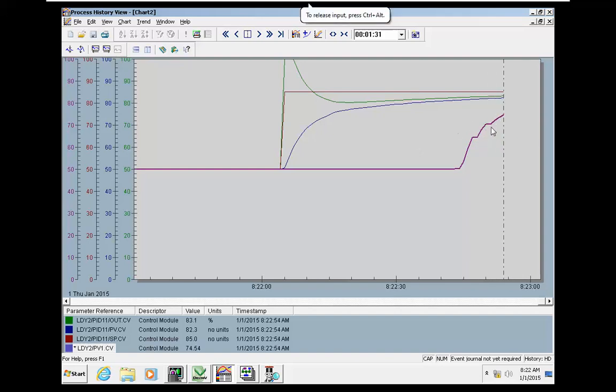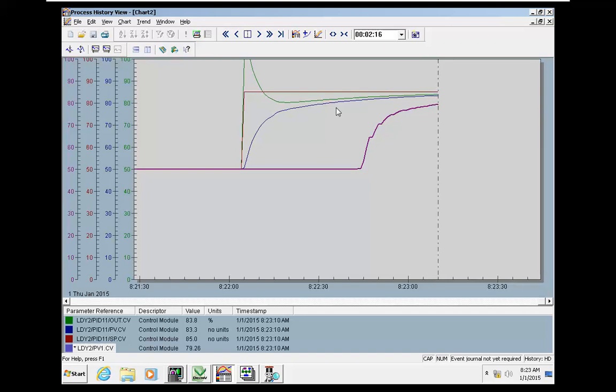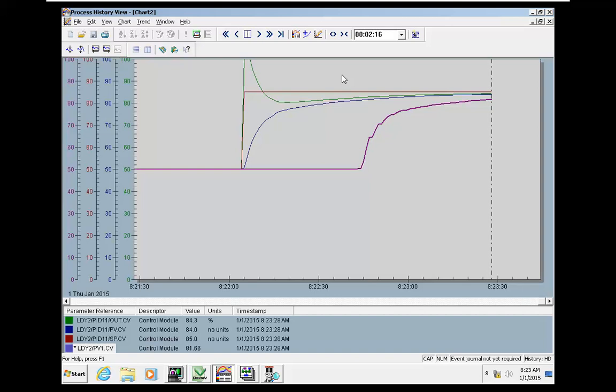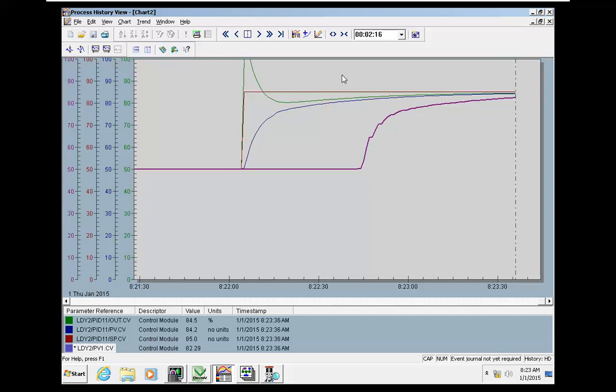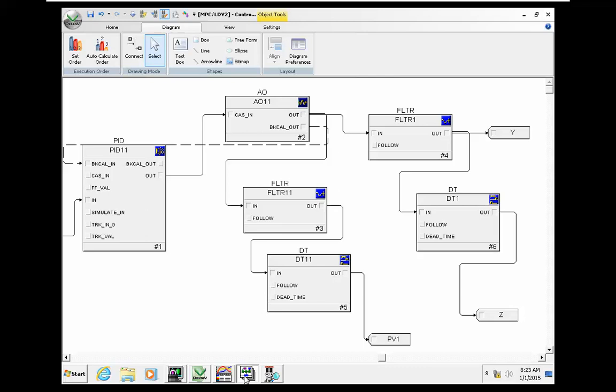The actual process value has a very large dead time, but you can see the actual process value is following the set value and all the control parameters are normal and acceptable. There is no overshoot and no undershoot — the response is acceptable. In this example, the time constant is 10 and the dead time is 40, which is four times the time constant, and you can see this strategy handles this case very easily.